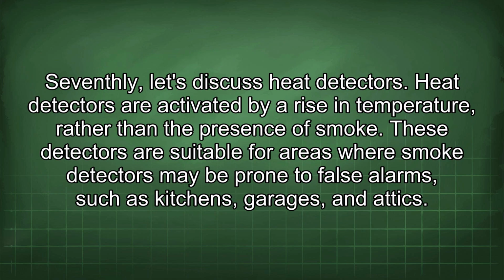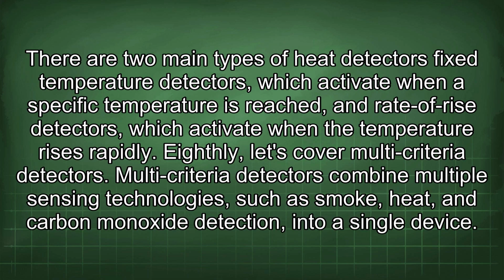Seventhly, let's discuss heat detectors. Heat detectors are activated by a rise in temperature rather than the presence of smoke. These detectors are suitable for areas where smoke detectors may be prone to false alarms, such as kitchens, garages, and attics. There are two main types of heat detectors: fixed temperature detectors, which activate when a specific temperature is reached, and rate of rise detectors, which activate when the temperature rises rapidly.